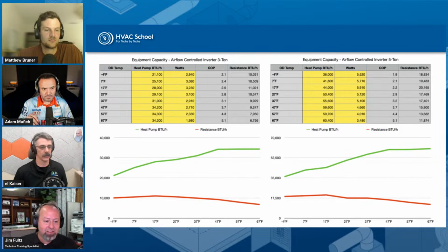So, just to clarify this, what you've been talking about so far has been thermal balance point. That's where we've been kind of starting off, and now you're transitioning over into economic balance point. Economic, I think, is what that's called, right? Balance point. And that's the thing there. We call them both balance points, but there is a difference between the two. And so maybe I can give a little definition of the economic balance point. We can head back to the thermal.